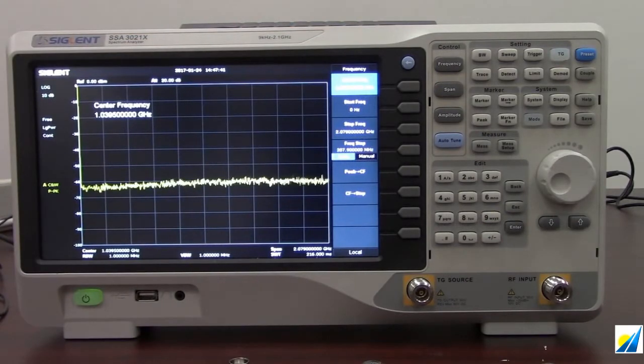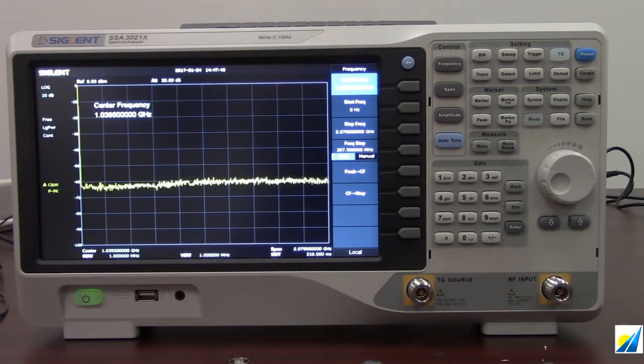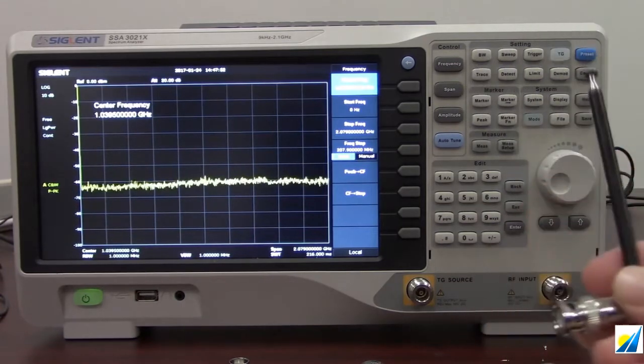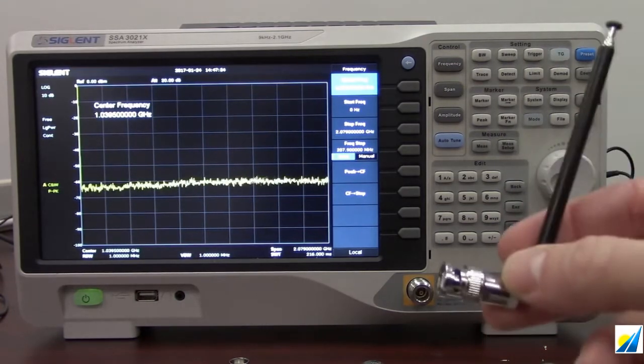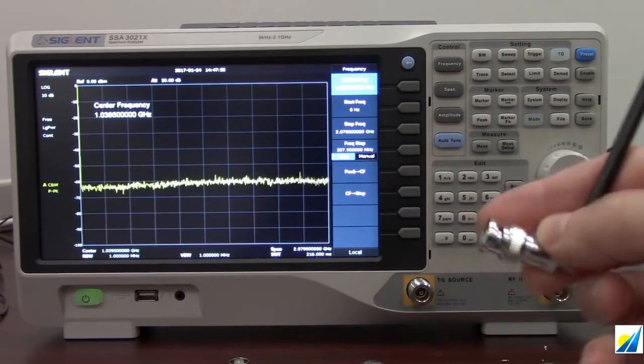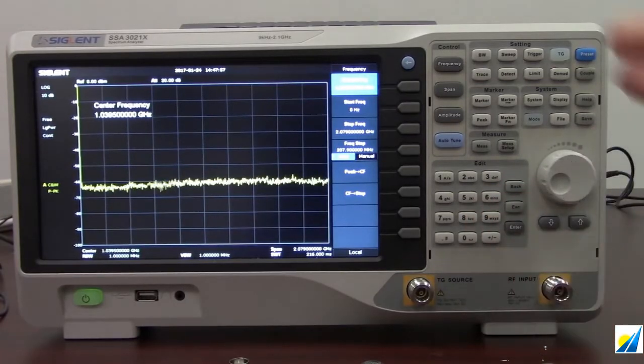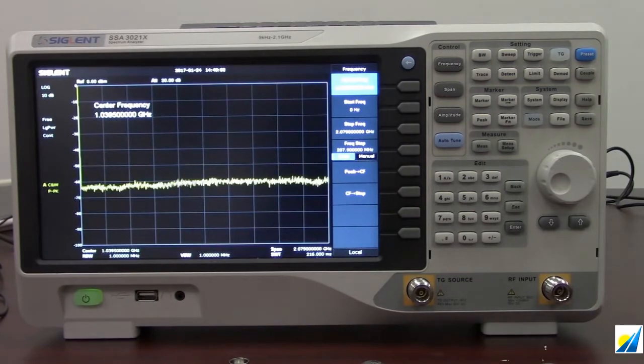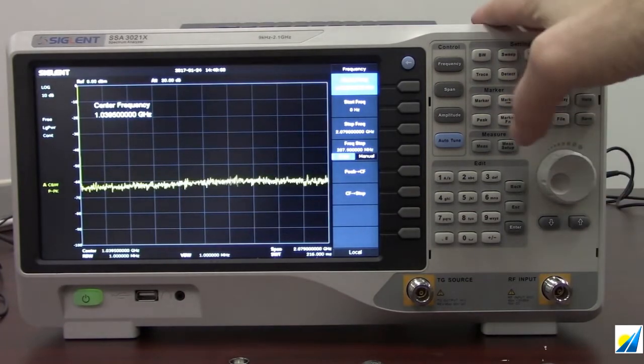I'd like to demonstrate a VSWR test for this components section. VSWR stands for voltage standing wave ratio measurement, and it is typically done on an antenna or antenna network. The VSWR is a measurement of the quality of the impedance match between the antenna network and a 50-ohm network.